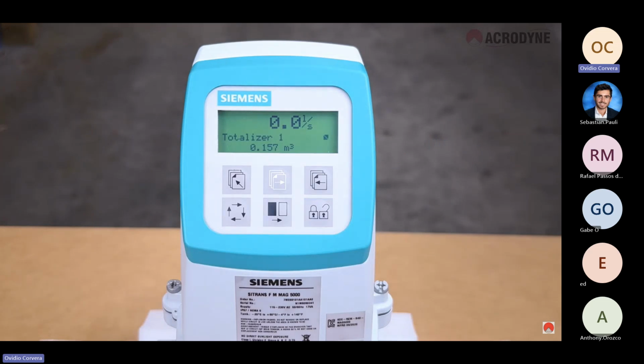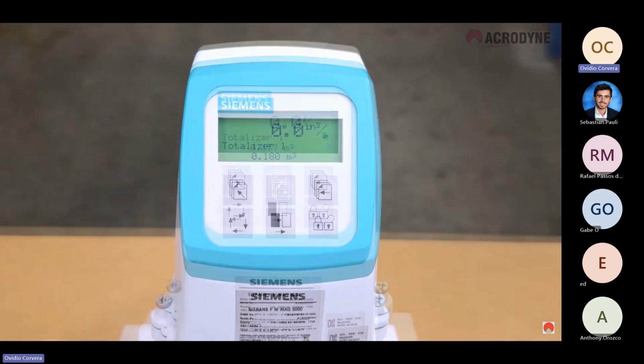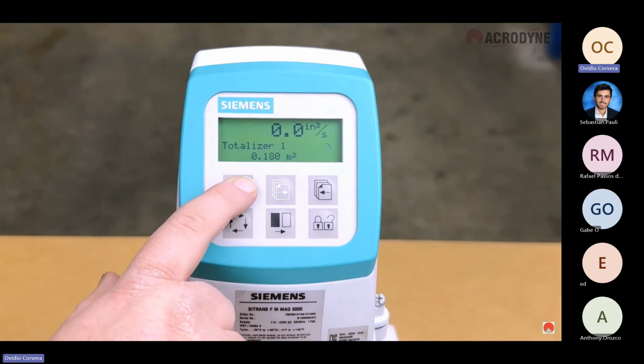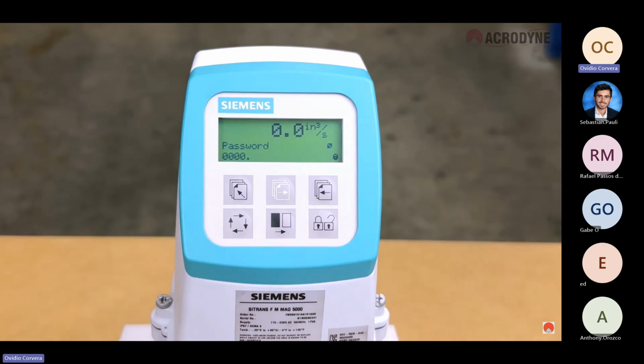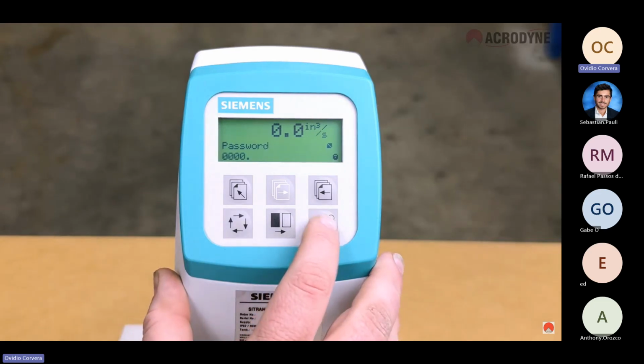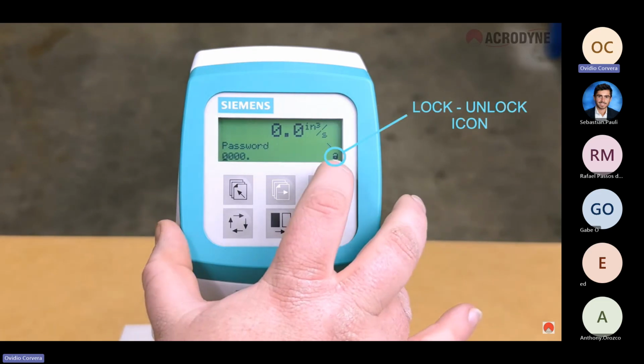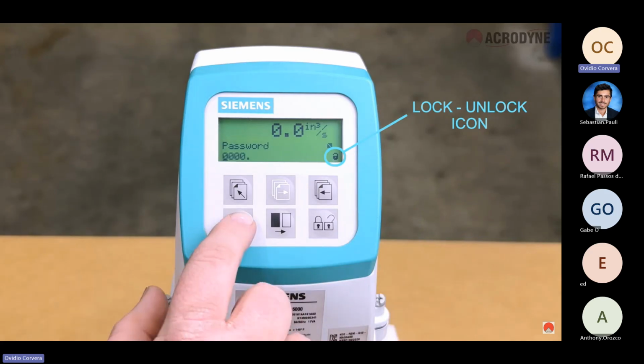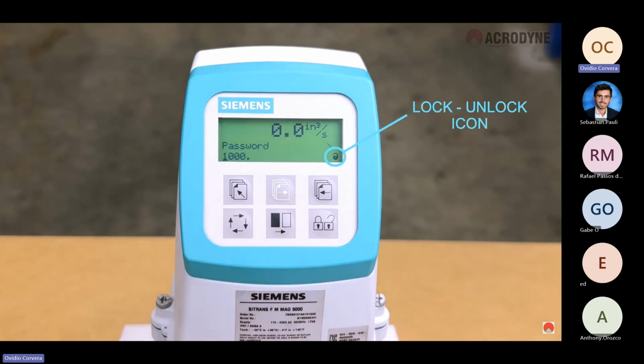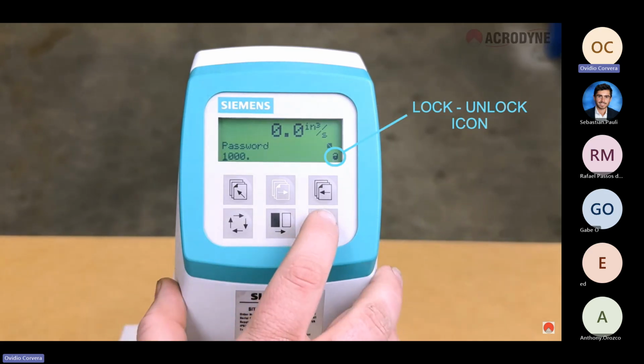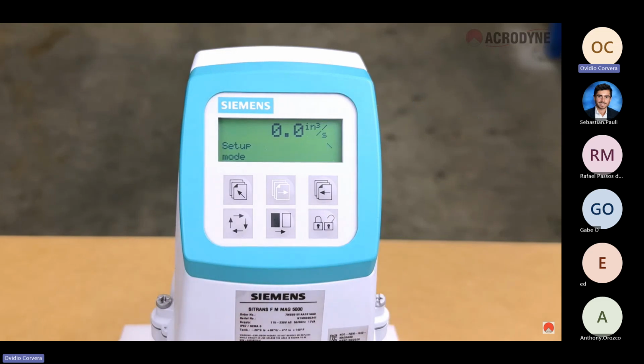Now that we are more familiar with the device interface, it is time to do some basic configurations. Hold down the top-up key for 2 seconds to bring up the password screen. Enter the 4-digit password. The default password is 1000. Ensure you change this password to secure your device in the field. To enter your password, press the lock or unlock key. The full programming mode is now available. To change the basic settings again, press the lock-unlock button.